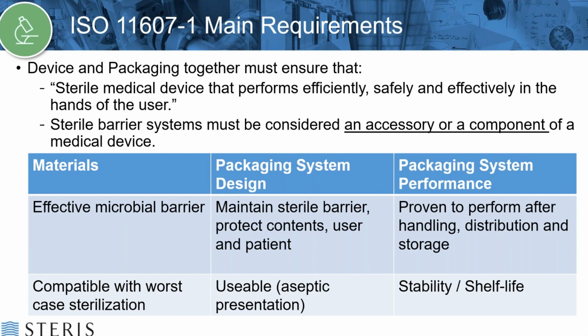The packaging system should be designed to maintain the sterile barrier, protect the contents, the user, and the patient. And then it needs to also be designed to be usable, for aseptic presentation, to be able to present it to the sterile field without contamination. And then the performance of your packaging system should be able to perform through the standard handling, distribution, and storage of the product. And that includes stability or a shelf life study as well.